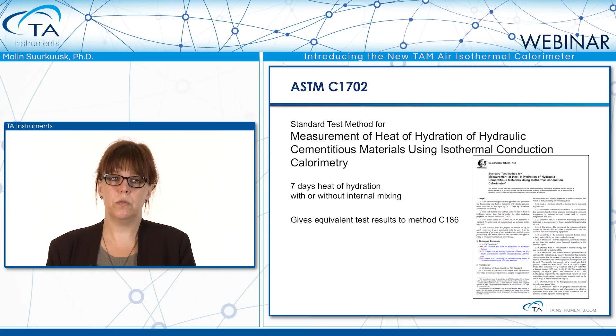I can give some notes on the sample size and the sensitivity of a calorimeter for measuring these 7 days of hydration from a cement. In the method, it states that the temperature in the cement sample should not increase more than 1 degree from the thermostat temperature. A larger sample may not comply with this method, as the heat produced when the cement is hydrating could warm the sample up, and hence the measurement can no longer be considered isothermal, as well as the kinetics of the process will be affected. But the sample needs to be large enough to produce enough heat to be measured reliably after 7 days.